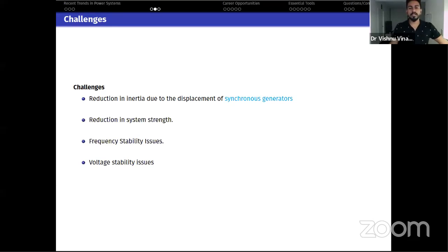The reason for that is that synchronous generators are designed in such a way that they can generate almost 200% of their rated current. That means they can supply twice their rated current if any fault happens in the system.